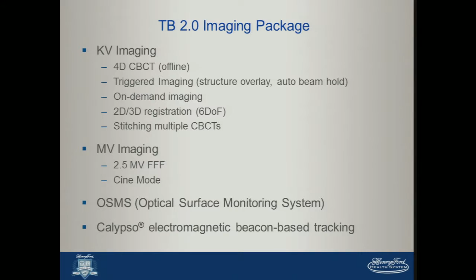The Edge TrueBeam onboard imager properties are as follows. I'll let you read some of these and try and pick out the highlights. CBCTs can be acquired at slow to fast rotations. So we use, for example, 3 degrees per second down to 1 degree per second, depending on the quality of the image you want and the structures you're trying to see. And fluoroscopic imaging options continue to be there. The MV imager properties, it's the new digital megavoltage imager. It has increased build-up to hopefully reduce the impact of scatter on the image, make that more uniform. It's got a larger 43 cm squared panel and supports high dose rate beams.